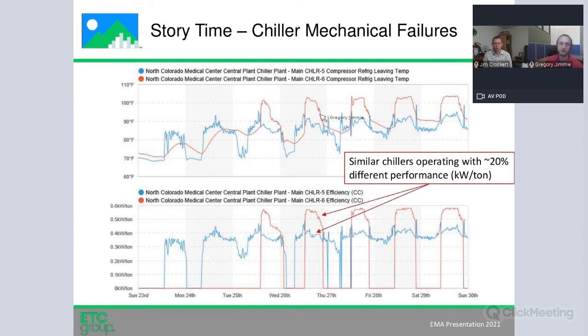We're talking 15 or so degrees there. And then that corresponds to a degraded or worse efficiency on that same chiller. To see 20 to 30% worse on these chillers was something that we were seeing pretty regularly. And we couldn't quite figure out exactly what was going on, but we could see that something was off. So we dove a little deeper. We got in on site.